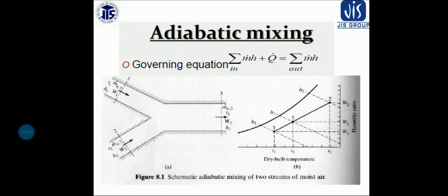If the air quantities are known in volume instead of mass, it is generally sufficiently accurate to use units of meter cube per minute in the mixing equation. The inaccuracy introduced is due to the difference in specific volume at the two initial states, which is small for most comfort air conditioning problems.